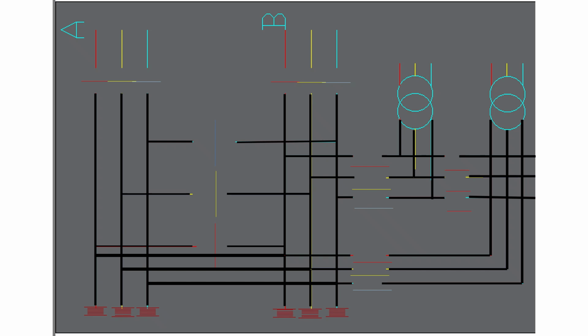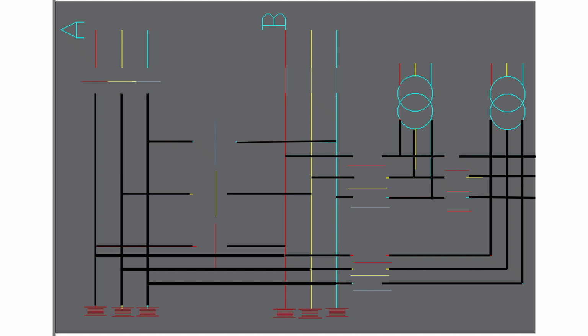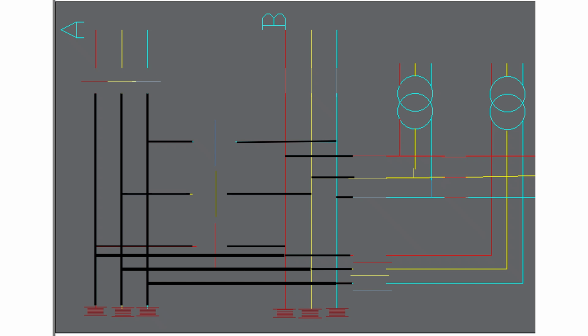Suppose you will take power supply from B. Black means it is in discharge condition. The supply is not available. Now you have to take power from B. A and B's incoming supply is available, but we are not taking power now. Now first we will take power supply from B. How? See. Now to get power supply from A, switch off B. How will you switch off B? You can open the first isolator of the transformer side of the B way.